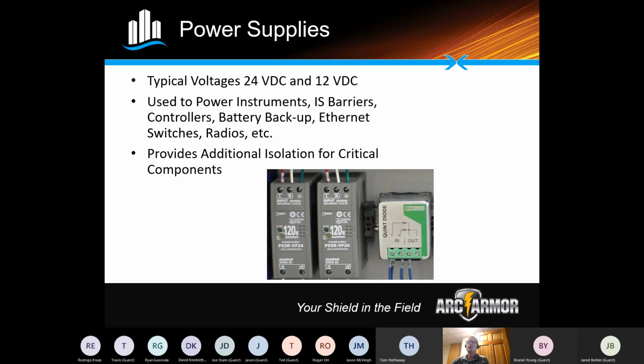Now, you've probably also heard, and I don't have a slide on this, what they call UPSs or uninterruptible power supplies. Those are normally 120 rated. They're big. They've got batteries inside those as well. They do generate a lot of heat. The one issue I would say with using a UPS, they're great in panels within buildings where the buildings have climate controlled temperature.